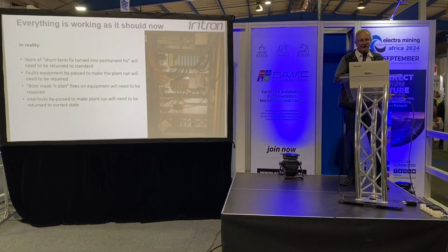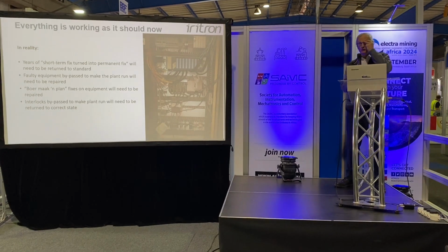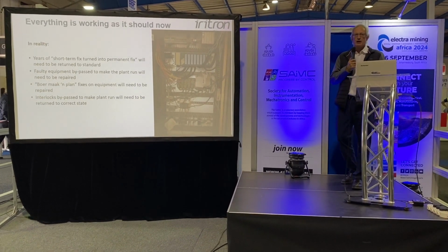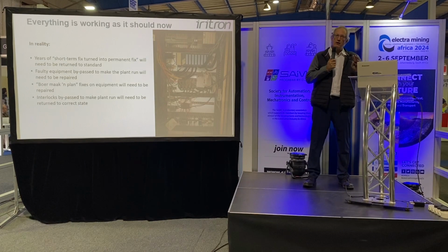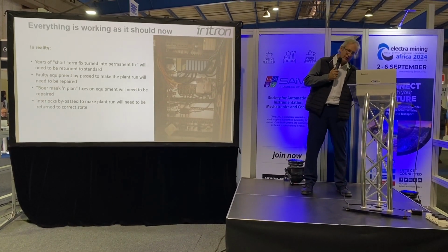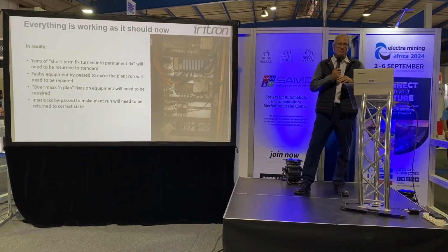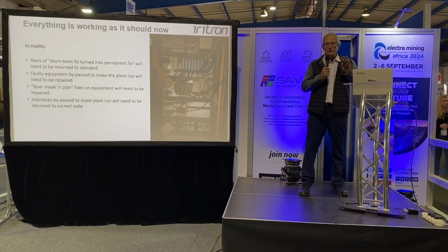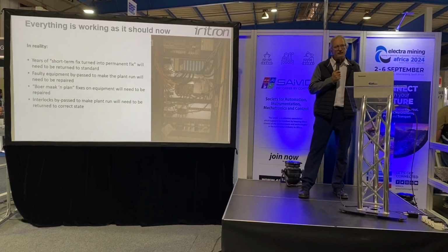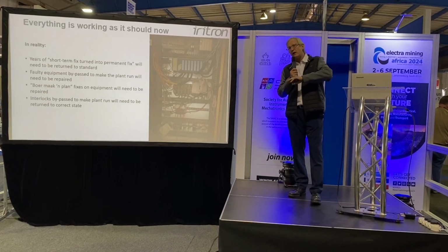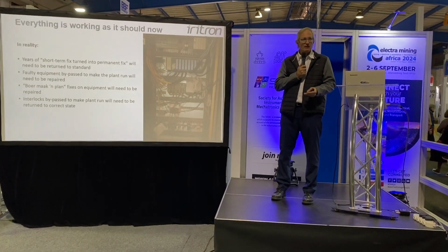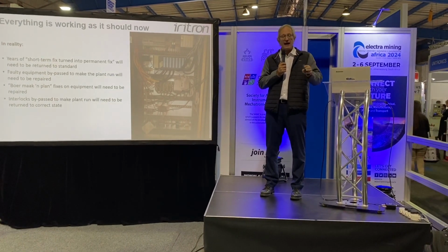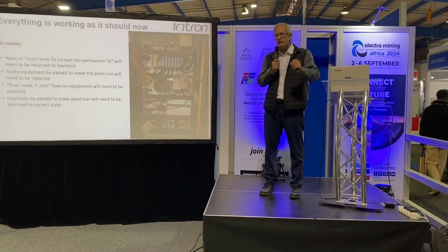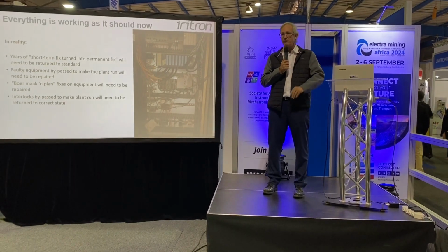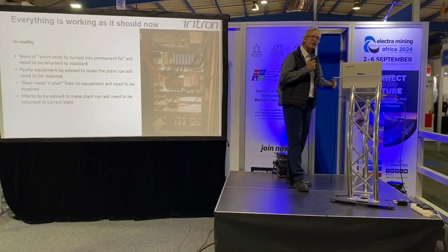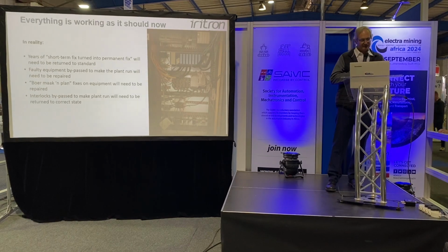Then there are the 'Boer maak 'n plan' fixes, right? We can't get it to work like it should, so we're making a plan. We're combining some stuff in the PLC, with some stuff in the SCADA, with some stuff in the communication layer, just to get this thing to work. We know it's not standard. We know it doesn't conform to the company standard or to best practice, but that's the only way we could get it to work at the time because the plant had been standing for 3 days. So now we fixed it, and it becomes a semi-permanent fix for the past 5 years.